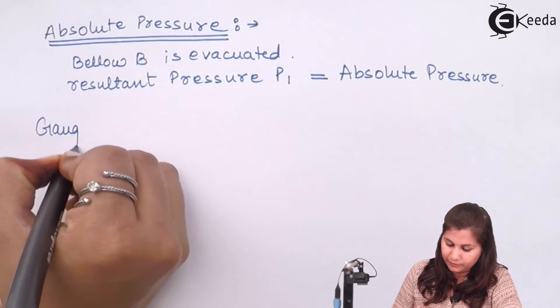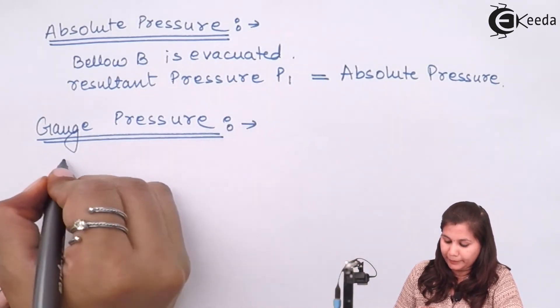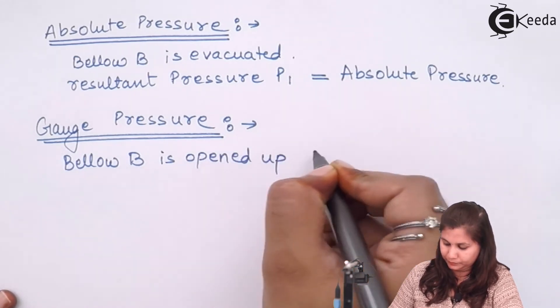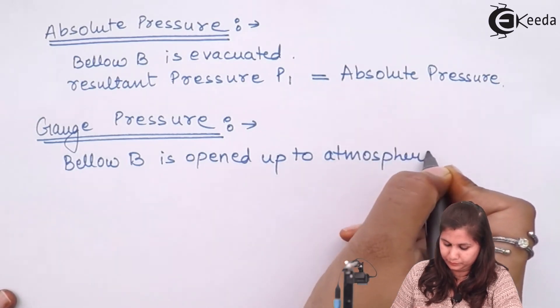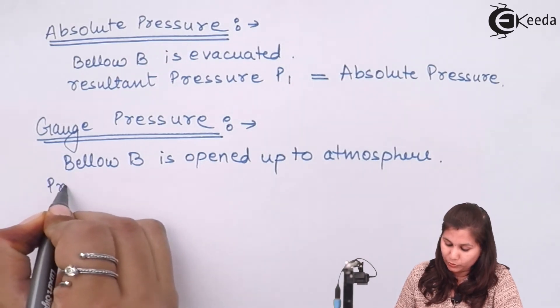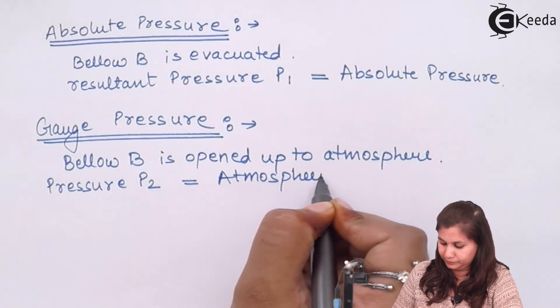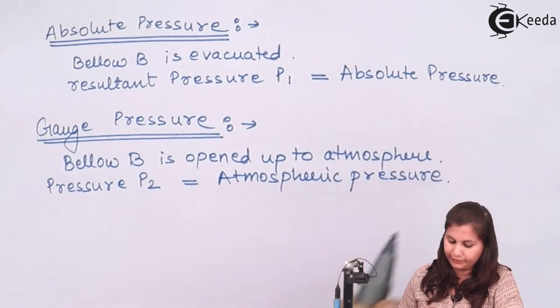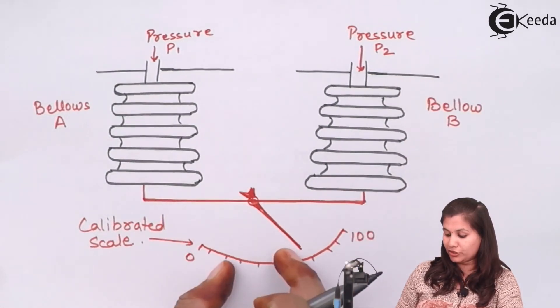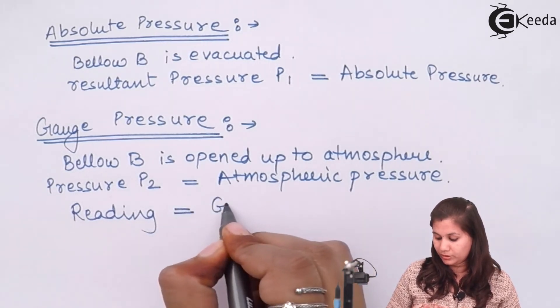For measurement of gauge pressure, bellow B is open to the air — so bellow B is opened up to the atmosphere, meaning pressure P2 is equal to atmospheric pressure. Therefore the reading which we are getting on the scale is P1 minus atmospheric pressure, which is the gauge pressure. So the reading of the scale is equal to the gauge pressure.